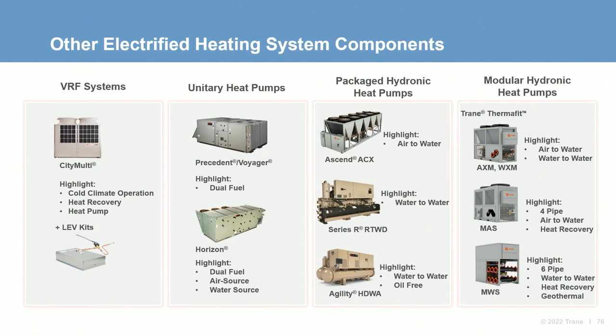We focused on electrified heating systems based on air-to-water heat pumps in this E&L, but heating systems can be configured with VRF, unitary, and water source equipment as well. Deciding on what system is right for a given building application generally considers first cost, performance and operating cost, as well as carbon footprint. While component performance comparisons can be telling, an 8760-hour building analysis is most revealing and should be used to compare alternatives.